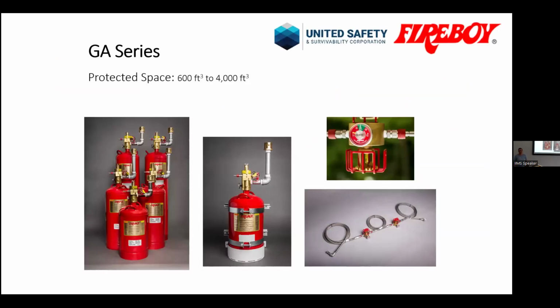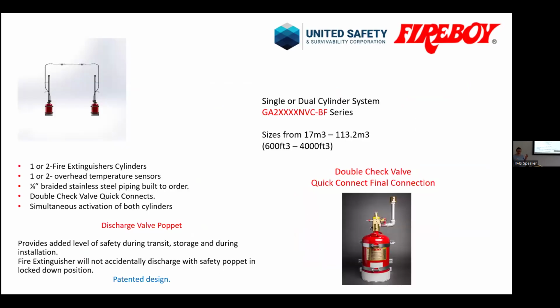Some of the bigger boats have a bigger engine room and require different size extinguishers, because the single cylinder MA range that we do only goes up to 51.5 cubic meters. So we also have a GA series range, which goes up to 4,000 cubic feet or 113.2 cubic meters. So you might come across those on bigger fishing vessels that have quite big engine rooms, some of the small commercial vessels, and some of the bigger pleasure boats.